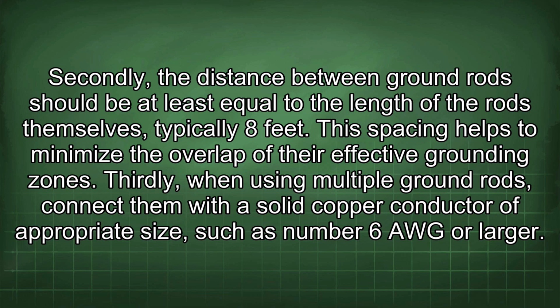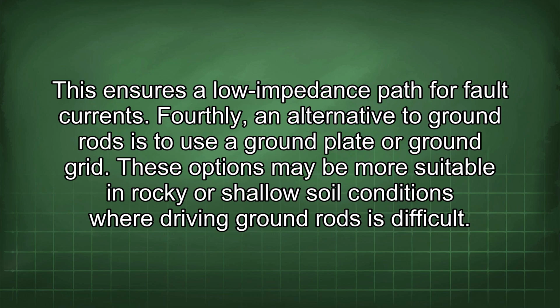This spacing helps to minimize the overlap of their effective grounding zones. Thirdly, when using multiple ground rods, connect them with a solid copper conductor of appropriate size, such as number 6 AWG or larger. This ensures a low impedance path for fault currents.